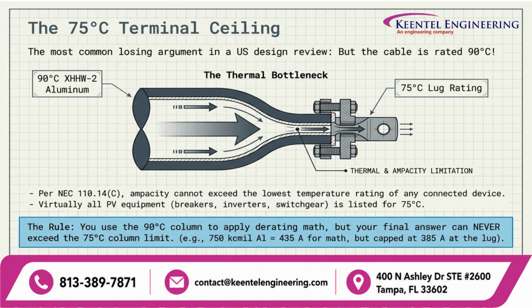A widespread misconception among designers is assuming they can run a 90 degree C rated cable at full 90 degree C ampacity. Per NEC 110.14(C), conductor ampacity cannot exceed the lowest temperature rating of any connected terminal, breaker, or switchgear, which in utility PV is universally rated for 75 degrees C. You can use the 90 degree C ampacity column as your starting point for derating calculations, but your final allowable current can never exceed the 75 degree C column limit.